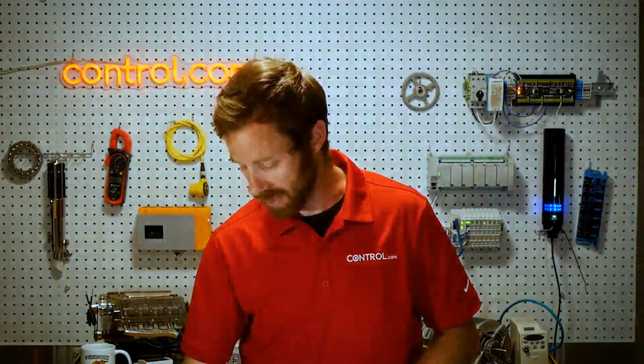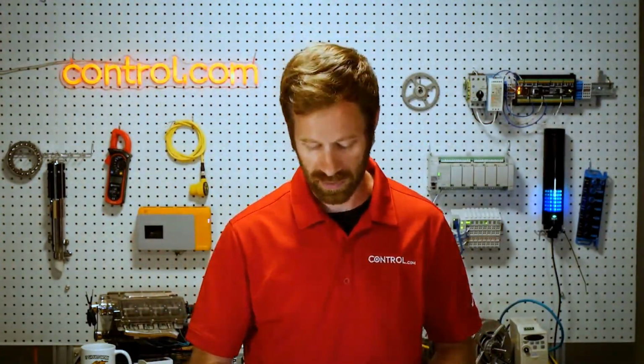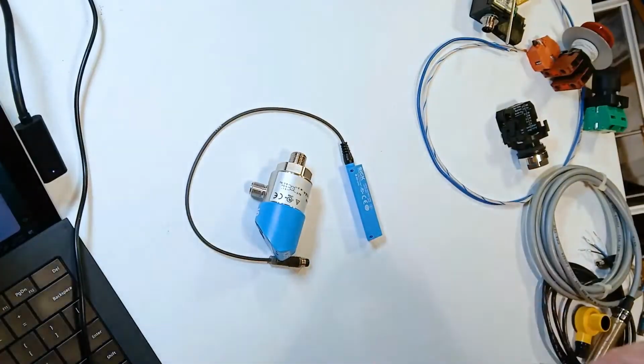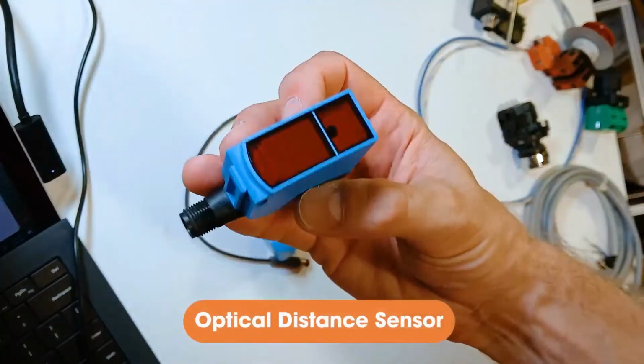But with IO-Link, we can read all of the data that's been previously saved to a sensor, saving us a lot of time. If we need to replace that sensor or duplicate a system, we can just copy all of those parameters into a new sensor. There's a couple of examples of IO-Link devices. Here is one that is an optical distance sensor.